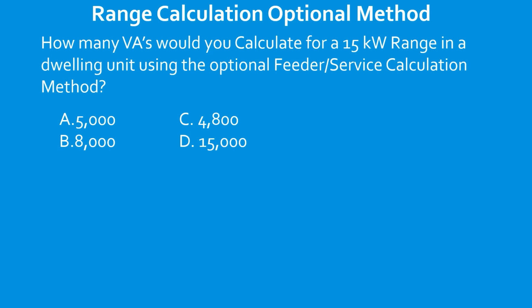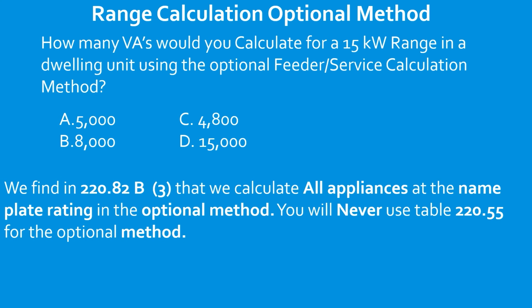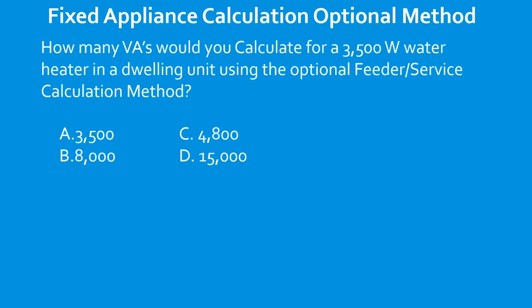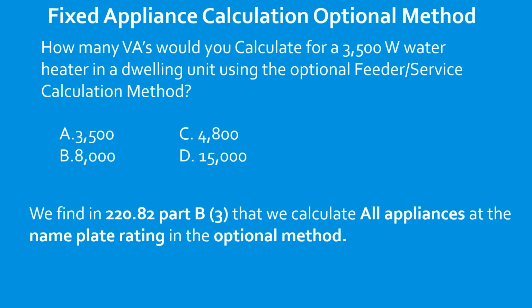How many VAs would you calculate for a 15 kW range in a dwelling unit using the optional feeder and service load calculation method? We find in 220.82(B) in Part 3 that we're going to calculate all the appliances at the nameplate rating. You'll never use the range table of 220.55 in the optional method. So you select 15,000. How many VAs would you calculate for a 3500 watt water heater in a dwelling unit using the optional feeder and service calculation method? Once again, 220.82 Part B3, we calculate all the appliances at the nameplate rating in the optional method, and it's going to be 3500.